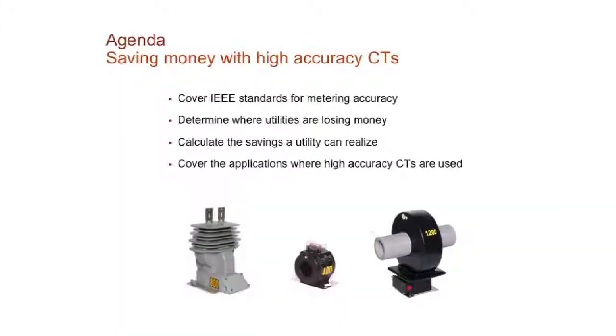So what we'll talk about today is we'll cover the IEEE standards for metering accuracy. Then we'll determine where utilities are losing money. Then we'll talk about how you can calculate what your utility could save by switching to high accuracy extended range current transformers. And then we'll cover the different applications where these high accuracy current transformers are being used and how you can implement them on your distribution grid.